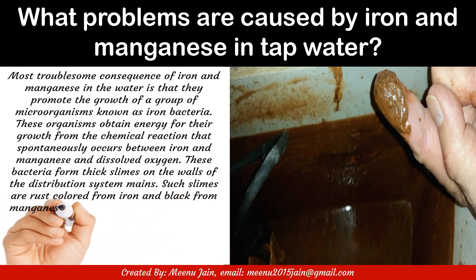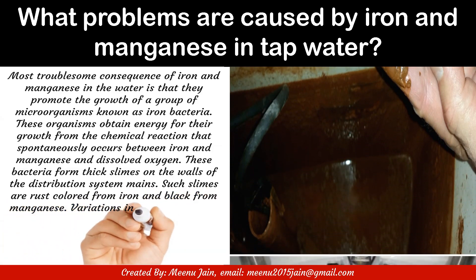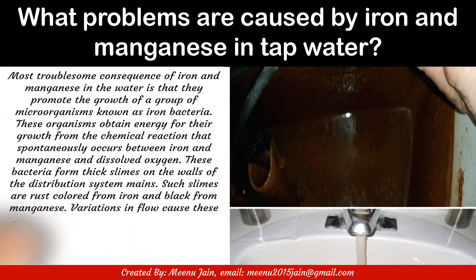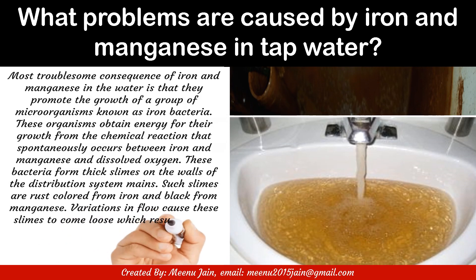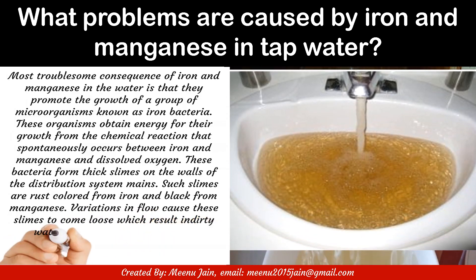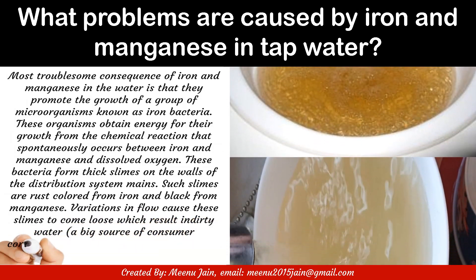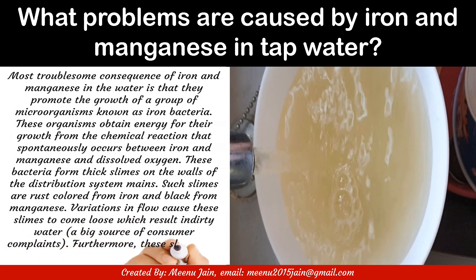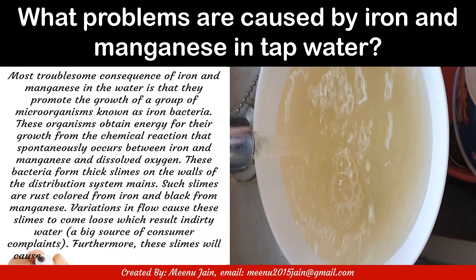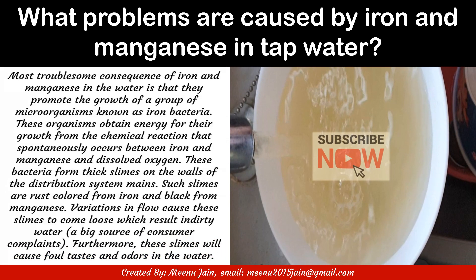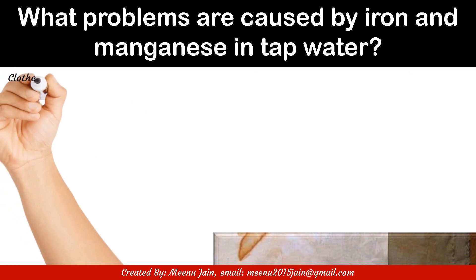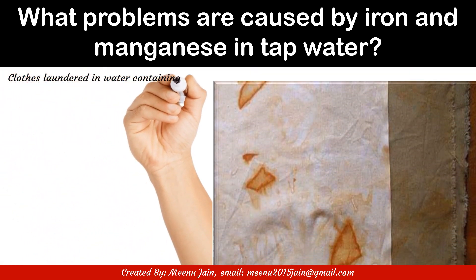These bacteria form thick slimes on the walls of the distribution system mains. Such slimes are rust-colored from iron and black from manganese. Variations in flow cause these slimes to come loose, resulting in dirty water — a big source of consumer complaints. Furthermore, these slimes cause foul tastes and odors in the water.